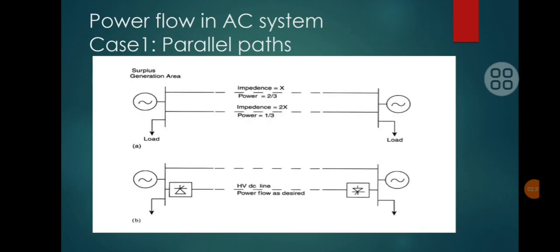Before we proceed towards understanding various FACTS controllers, it is imperative to know the structure of the existing power systems. Case 1 shows parallel paths. Here, figure A shows a system which is basically uncontrolled. There are two buses connected by two parallel lines, and the power flow from the surplus generation area to the other side depends entirely on the line impedances. The upper line has impedance X and the lower line has impedance 2X. According to the current division rule, the upper line will carry 2/3 of the total power and the lower line will carry 1/3 of the total power.